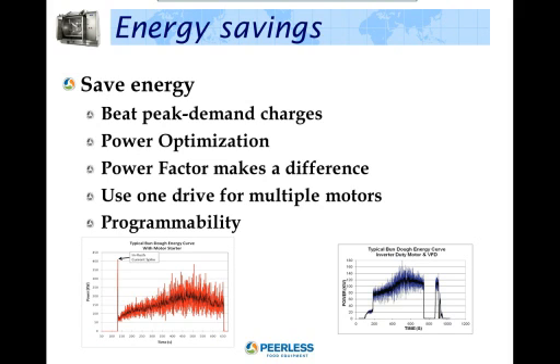Power optimization. Centrifugal loads offer the greatest potential for energy savings by using variable frequency drives to control speed. Energy consumption in centrifugal fan and pump applications follows the affinity laws, which means that flow is proportional to speed, pressure is proportional to the square of speed, and horsepower is proportional to the cube of speed. That means if an application only needs 80% flow, the fan or pump will run at 80% of rated speed and only require 50% of the rated power. In other words, reducing speed by 20% requires only 50% of the power.